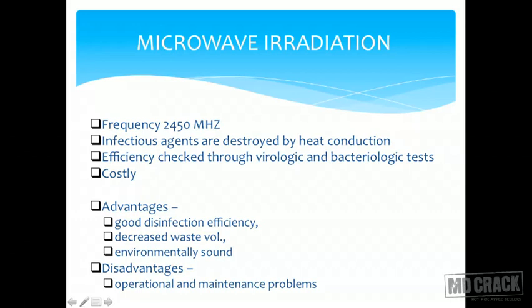The advantages of microwave irradiation are that it has good disinfection efficacy, it decreases the waste volume greatly, and it is environmentally sound. The disadvantages are operational and maintenance problems — since it is high tech equipment, the maintenance and operational component of the microwave will be high and can lead to problems.